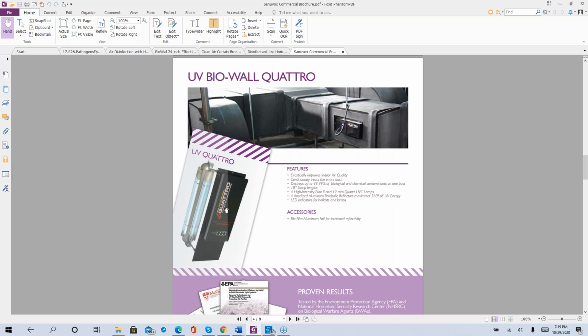You may or may not need to have the additional access panel to clean these, because you just undo the screws and physically remove the Quattro. The door switch may not be necessary because these come with a 110 volt plug that you could get your electrician to give yourself a duplex outlet above the ceiling near the duct. And of course, in order to remove it, you're going to want to unplug it.